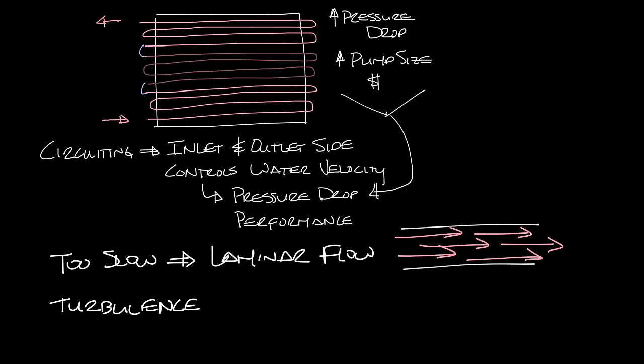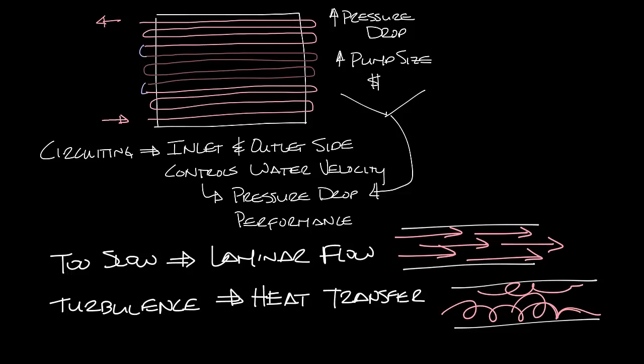Turbulence is needed for heat transfer. Basically the water splashing around the insides of the tube and making contact with the tube is what is transferring the heat from the water, in the case of a heating coil, to the tubes.